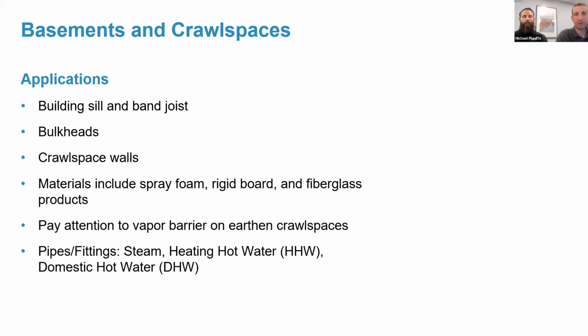Other items you might find in a crawl space would be heating piping, whether that be steam or hot water, hydronic heating mains, or domestic hot water. We don't want those items giving up heat to this unconditioned or semi-conditioned crawl space. So it may make sense to insulate the piping, both from an energy standpoint and also to protect against freezing in those areas.